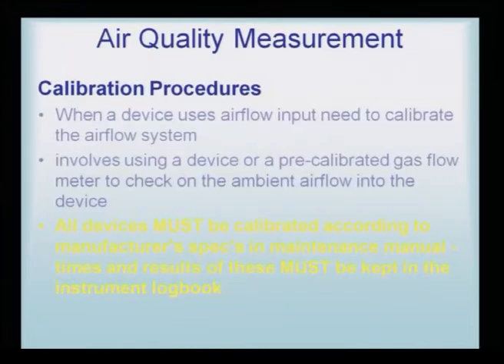All devices must be calibrated according to the manufacturer's specification in the maintenance manual. Times and results of these must be kept in the instrument logbook. It is important to have an instrument logbook to be able to see when the machine was validated and whether it is working in proper condition or not, because any machine can go wrong anywhere. It is important that these are kept up to date with all the regular checking of the machine, so that it can be taken that the machine is working in a normal and precise manner.